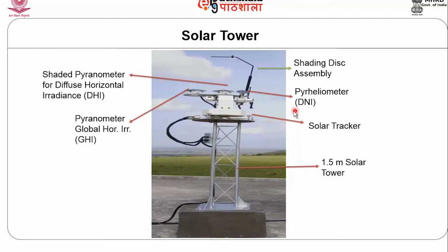This is the pyrheliometer. You can take direct or beam radiation, normal radiation. Here is the shading disc assembly, which you can operate to take a measurement for diffused radiation, and this pyranometer will directly give the global radiation also. This is the solar tracker.